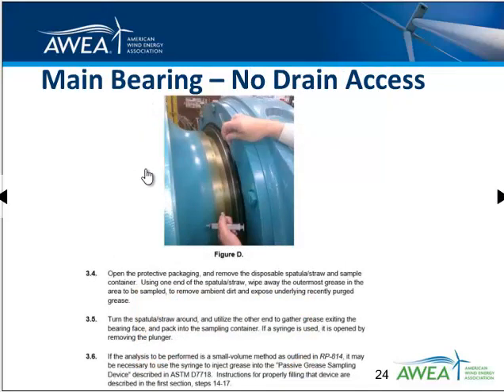When there is no drain access, it's important to first clear away any grease that's been sitting there for an extended period of time, because it has a tendency to trap particulate, dirt, and so forth — we don't want that in the sample. We obtain the sample from the grease lying underneath, hopefully grease that's more recently exited the bearing housing and has information about the condition of the grease, wear particles generated, and any contaminants present inside the housing.